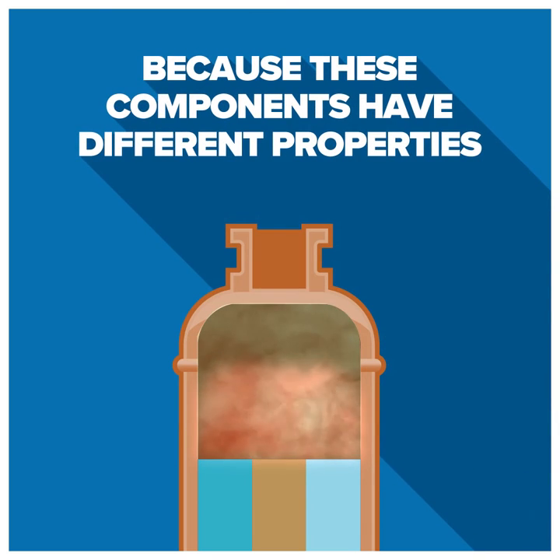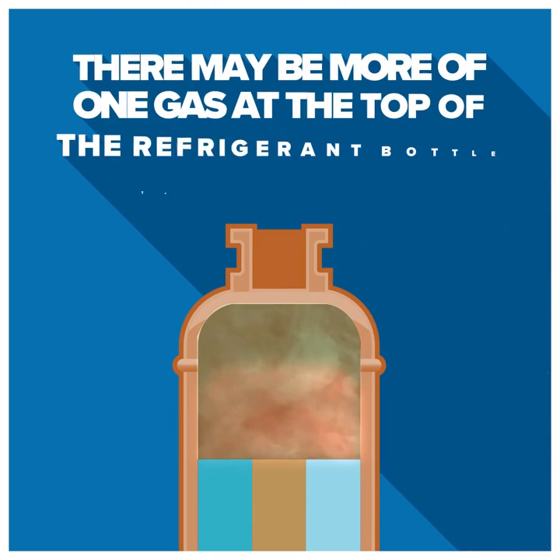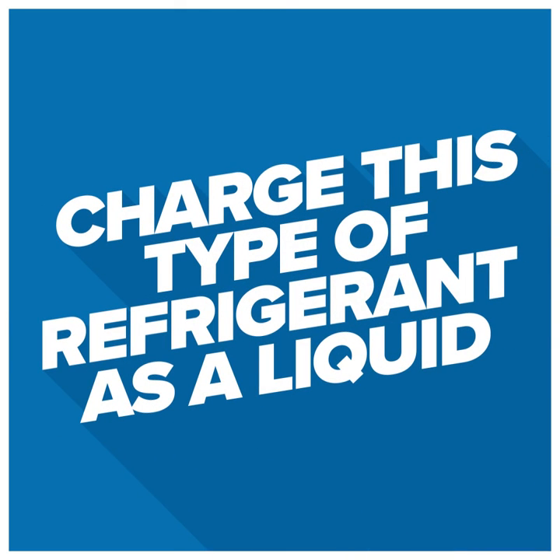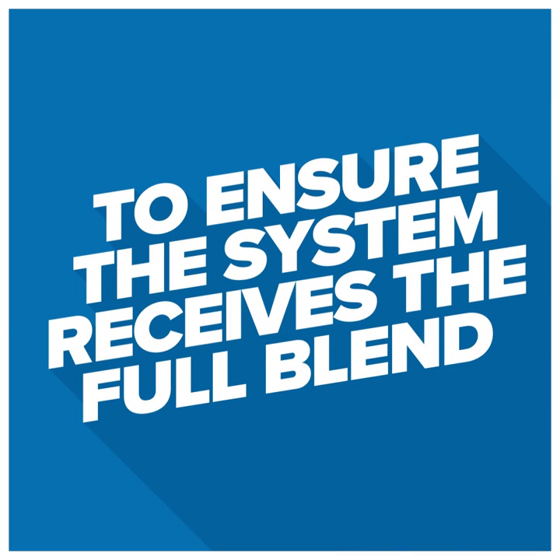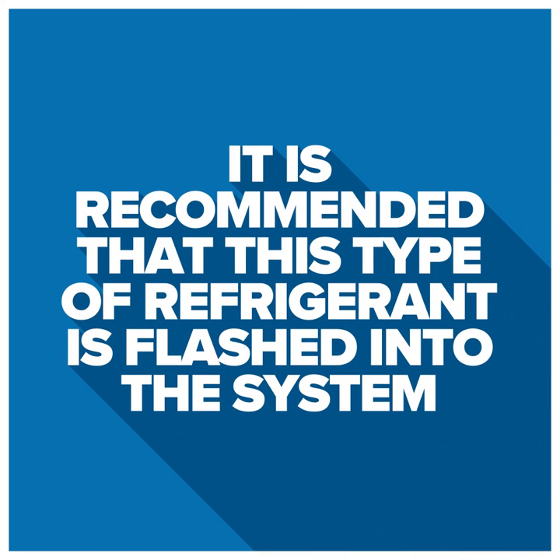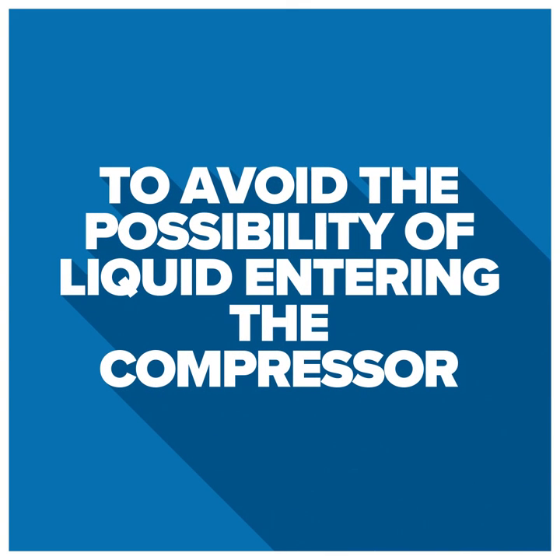Because these components have different properties, there may be more of one gas at the top of the refrigerant bottle than the other. This is why it is important to charge this type of refrigerant as liquid to ensure the system receives the full blend. It is recommended, however, that this type of refrigerant is flashed into the system to avoid the possibility of liquid entering the compressor and damaging that compressor.